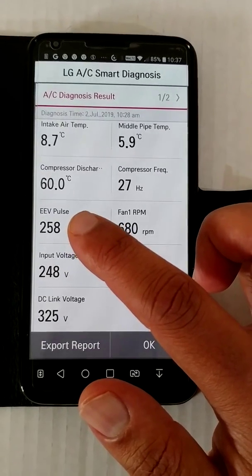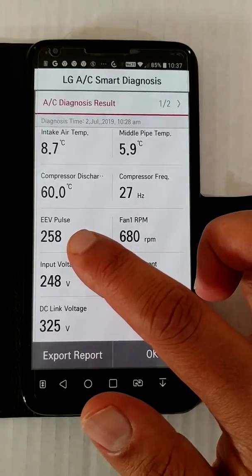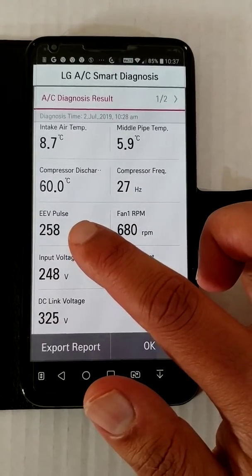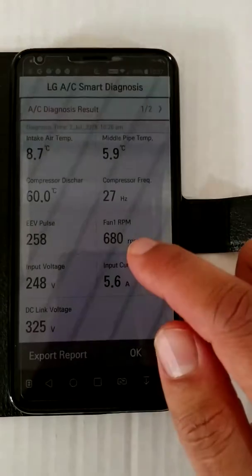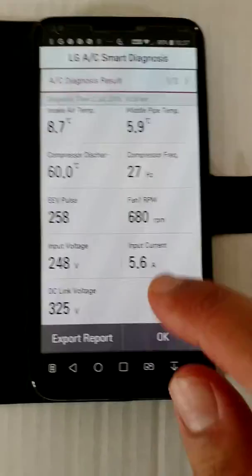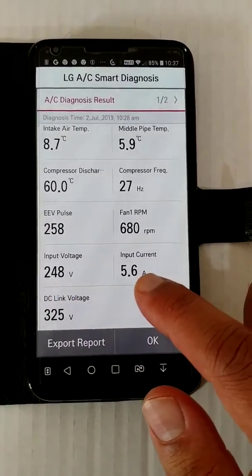Because it's an inverter unit, the orifice of the expansion valve is varied depending on how fast the compressor is rotating and how fast the refrigerant is flowing through the circuit. The outdoor fan is running at 680 RPM, input voltage is 248 volts, and the current is 5.6 amps.